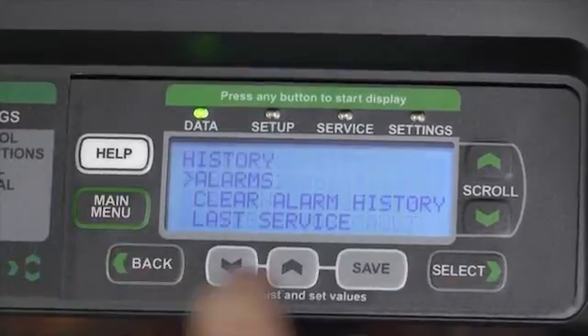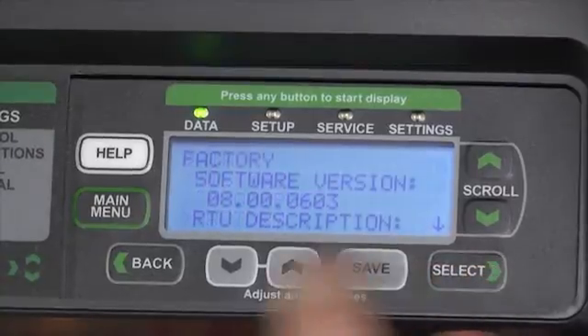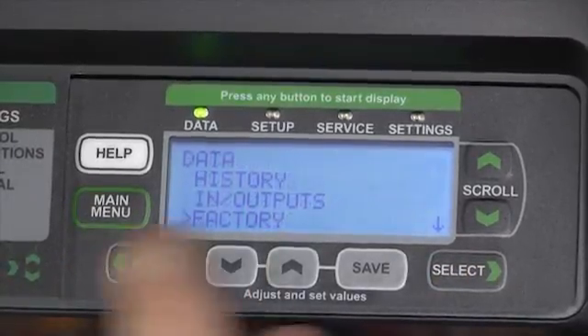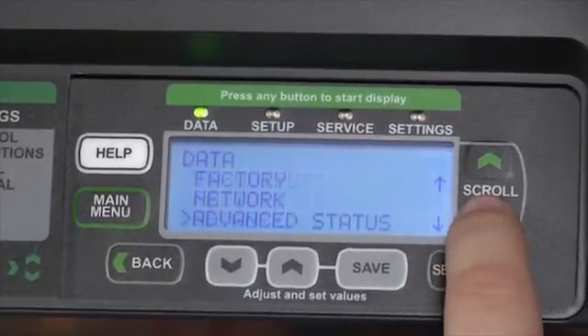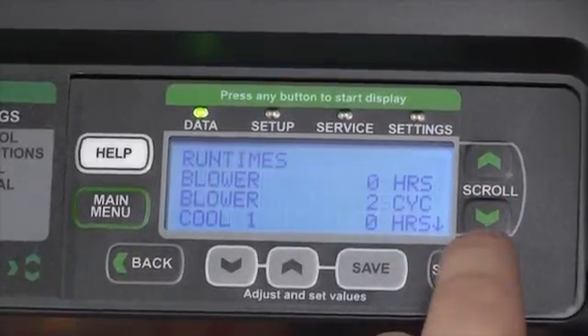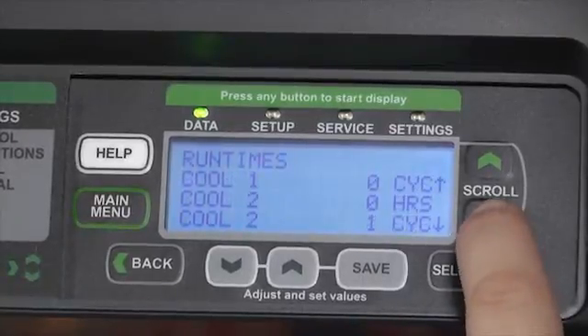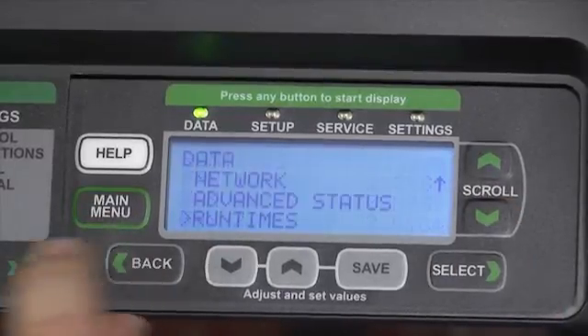Pressing the Back button again will take us back one menu item at a time. We can look at the factory information for the software currently on the control board. In the Data menu, we can also scroll down to Advanced Status or Run Times, and use the Select button to view the hours. As we can see for Cooling 1, there are zero hours, indicating that we just replaced the first compressor. Pressing the Back button will take us back one screen at a time, or the main menu button will take us all the way back to the home screen.